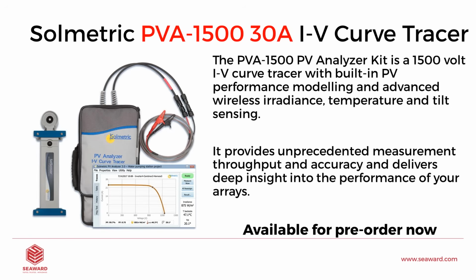However, the instrument is quite large, okay, and also it needs an on-site PC to work, and also the instrument is approximately $9,000. So the way we kind of see things and the way the partnership works is that you could give the Solar Utility Pro to all of your test crews and perhaps have one or two PVA 1500s that you use to really get down into the nitty-gritty of what the problem is. So whereas the Solar Utility Pro does not require an on-site laptop, it's very rugged, it's quite light in comparison, it'll give us VOC, ISC, temperature, and irradiance.